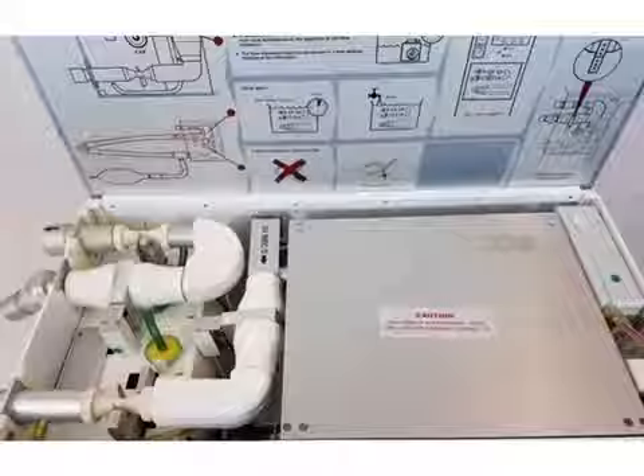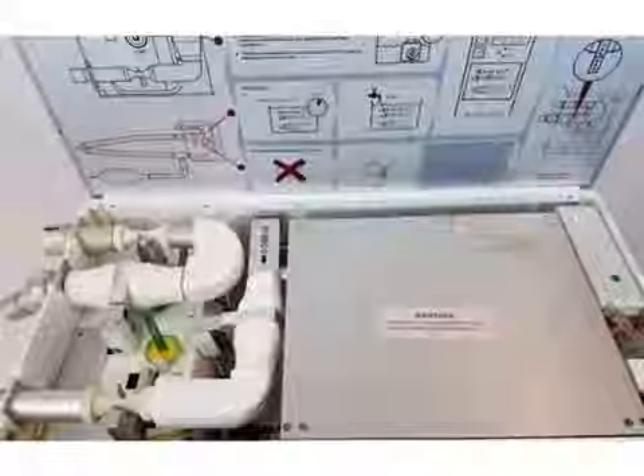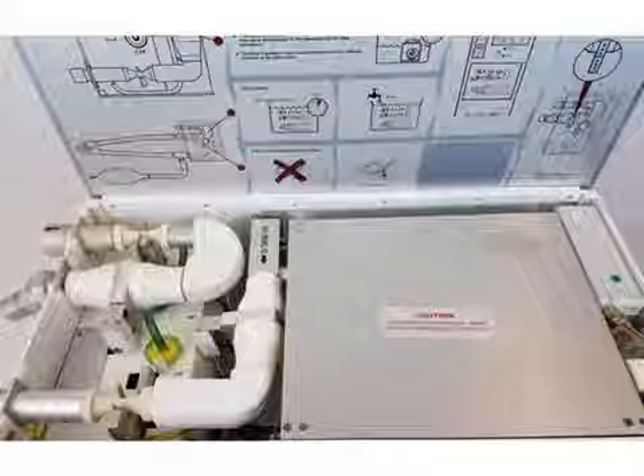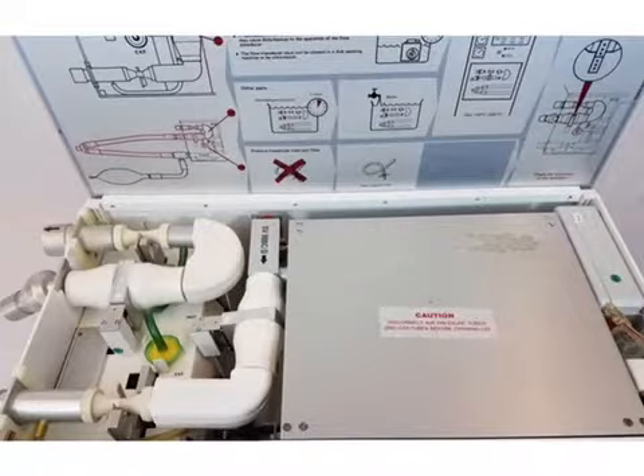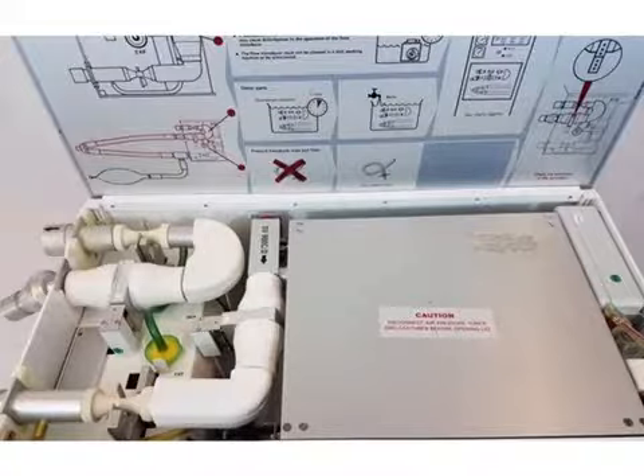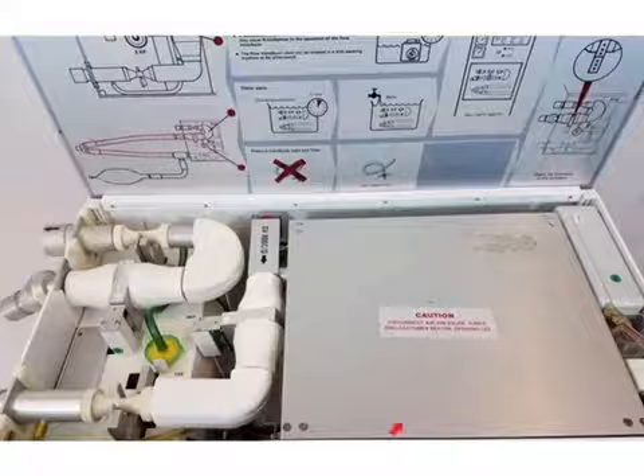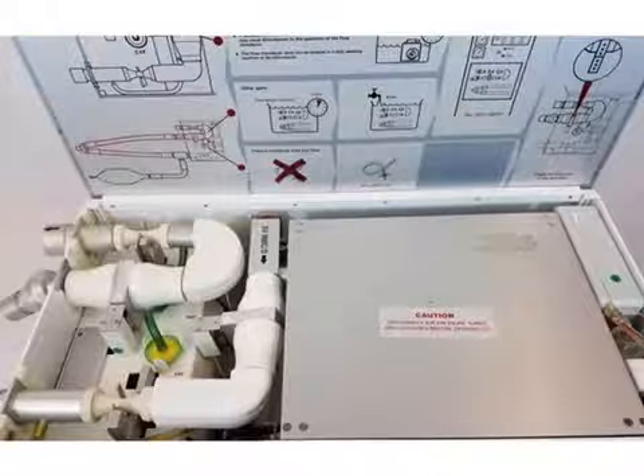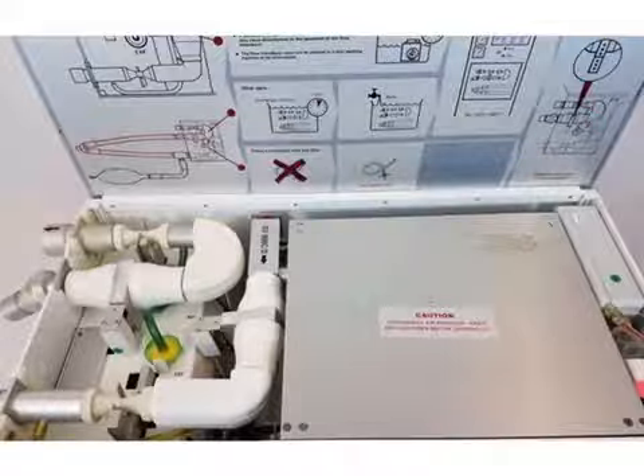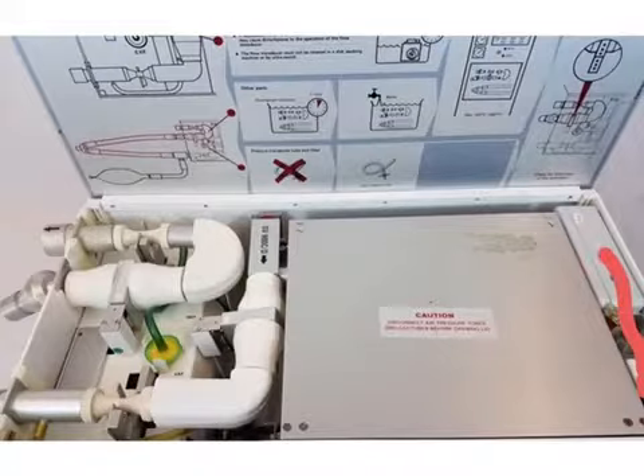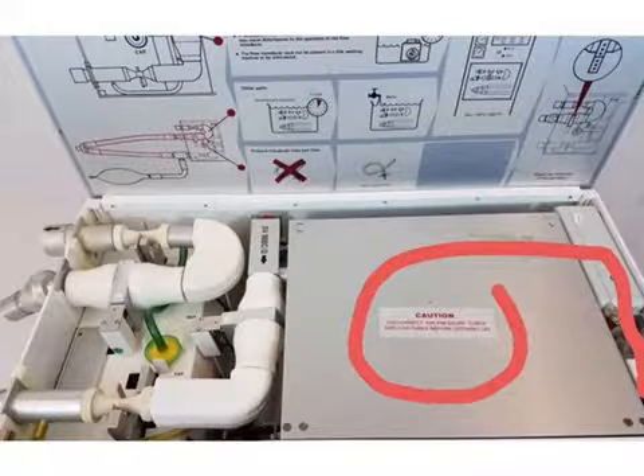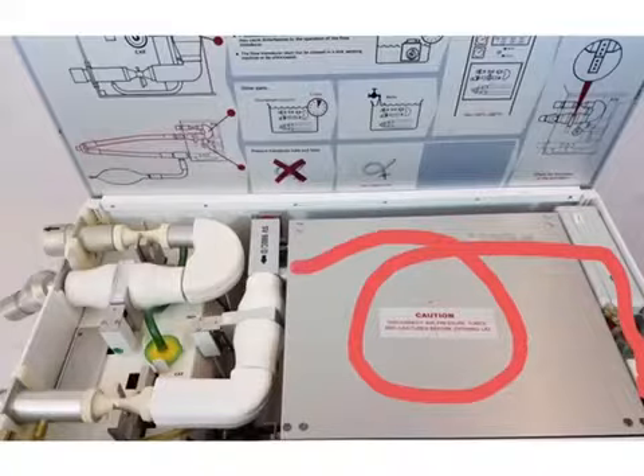Then once it goes to the O2 cell, it goes through here. This is a bacteria filter. Then the gas travels over here to the left and goes inside this. This is my bellows, which is held under a constant pressure, and the gases are mixed if you're using a mixed gas mixture. The working pressure is set by a screw that sits down here. It's on the front of the screen, and you'll see it from the front of the machine. Now if we draw the gas, it's coming from my gas inlets, going through the O2 cell, through the bacteria filter, and then it's mixing in the bellows here, and then it's going to go right out here to the left side.